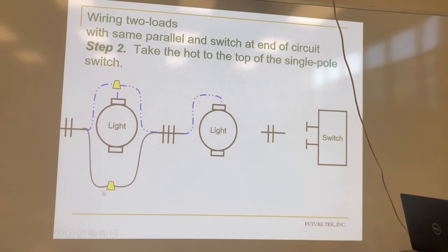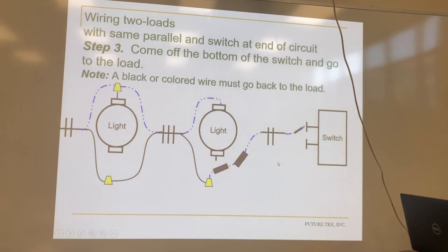Then our hot, we're going to tie together to the black one on this one, tie together here, to the white on this one. We're identifying this one as a hot, the white wire. And then our load here. And then also, this is a 12-3, so there's a red wire in it, right? So that red wire is tying in right here to feed this light as well. See that?